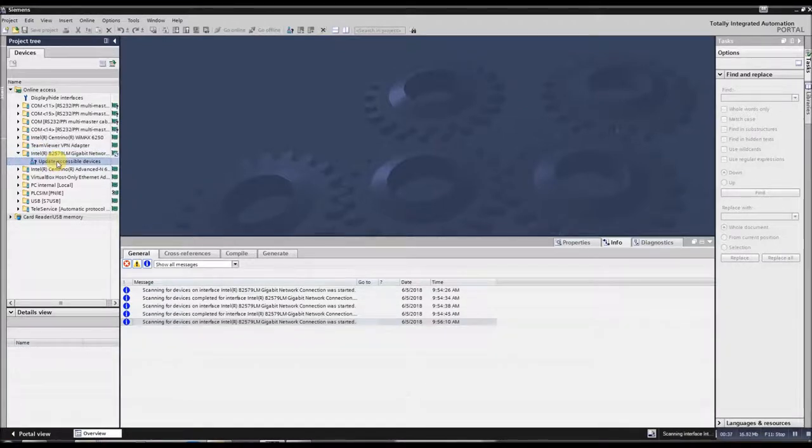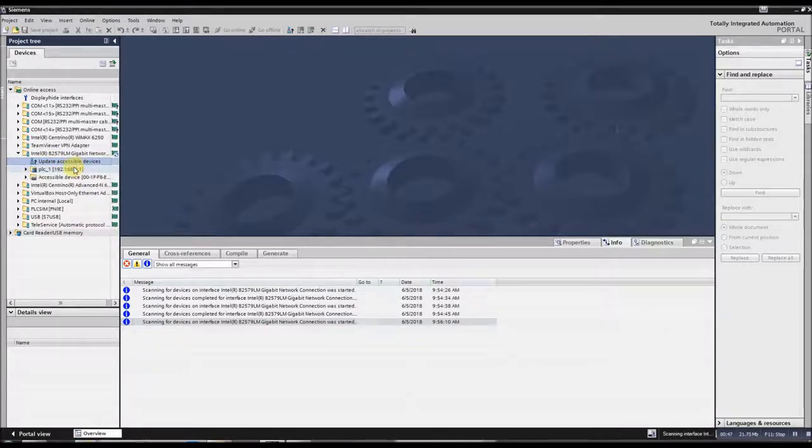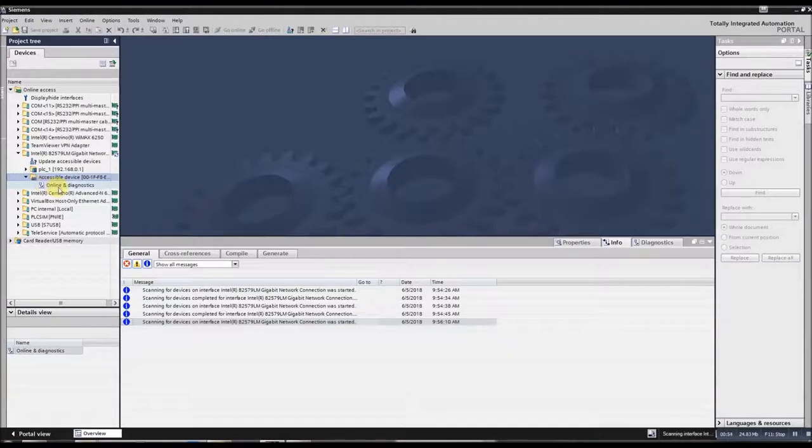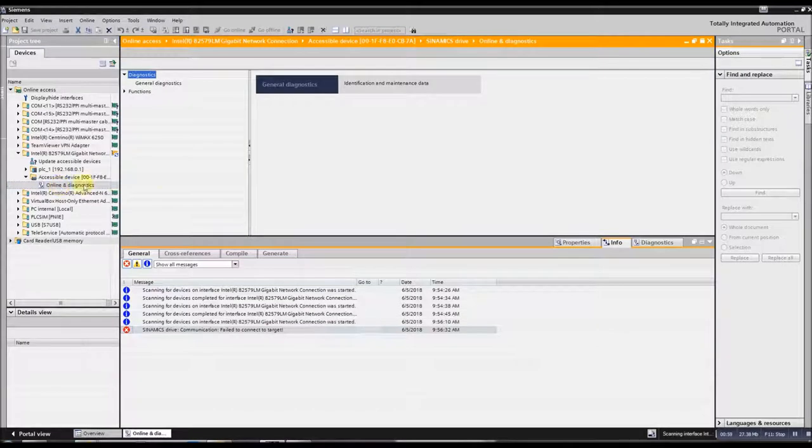Now, my G120 is completely factory reset, so it should only have a MAC address. The reason I'm showing you this is if your G120 doesn't have an IP on it physically, then you can't do an upload. So this would be something you would need to either ask your customer or if you just want to set an IP and then change it later. This is just the fastest way to get an upload of that G120.